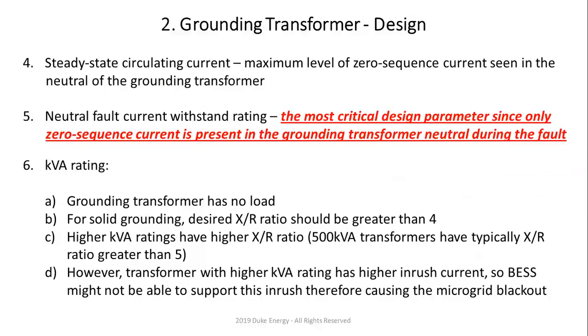So here's the key thing. The KVA rating is the last thing that you worry about, because it has no load, right? And for solid grounding, your X over R ratio should be greater than 4. So the higher KVA ratings have higher ratios. I can tell you 500 KVA transformers, this is from our 15-year experience, have an X over R ratio greater than 5. So in addition to doing the analysis that you need to do, you have to understand how the X over R ratio affects your fault currents.